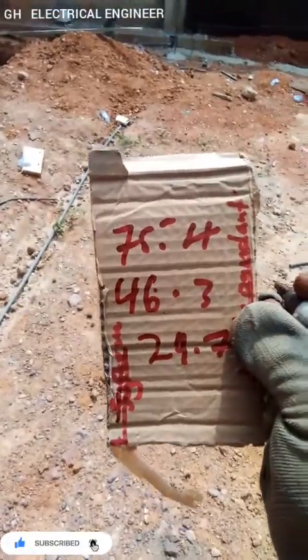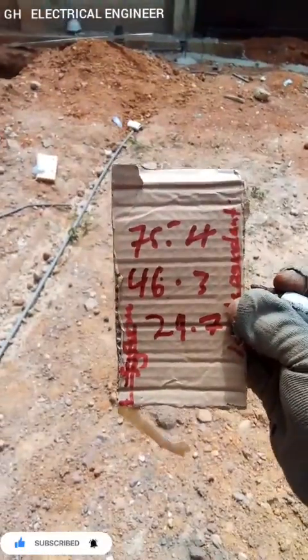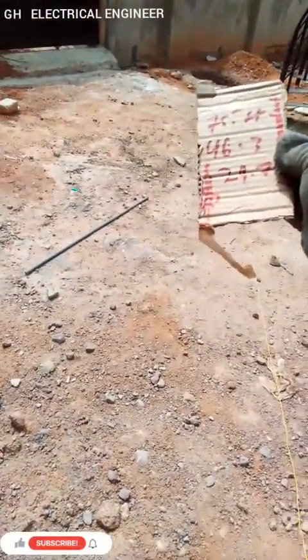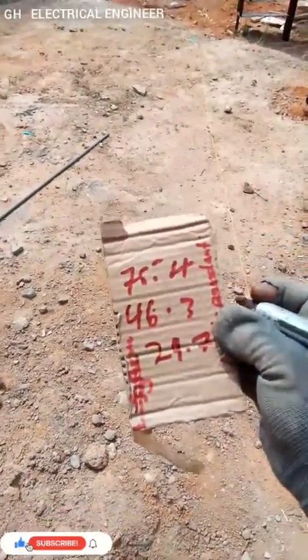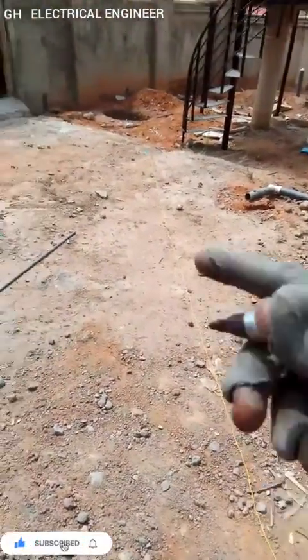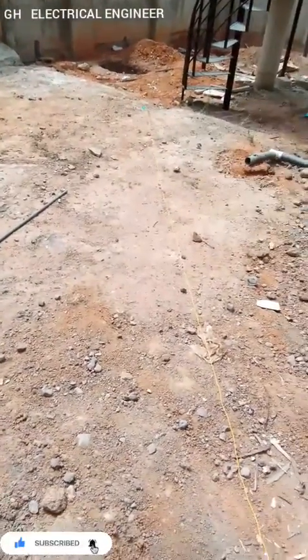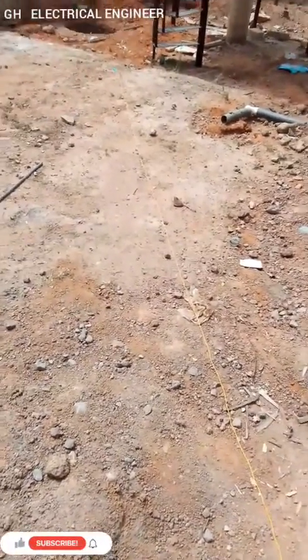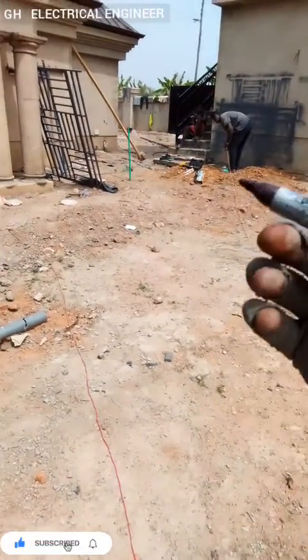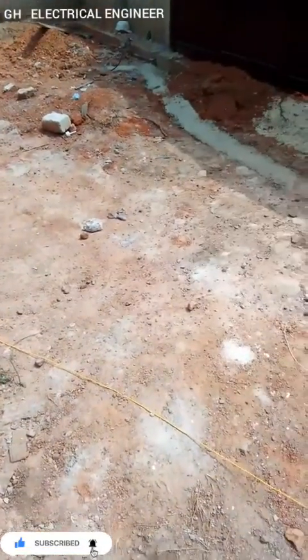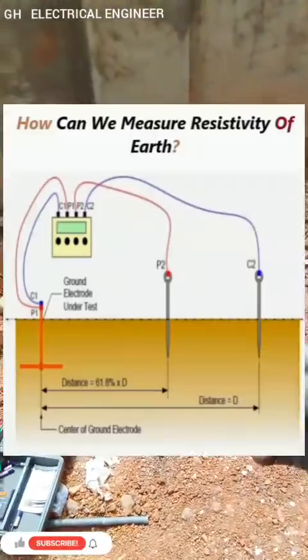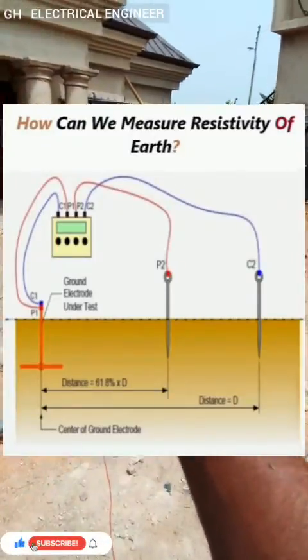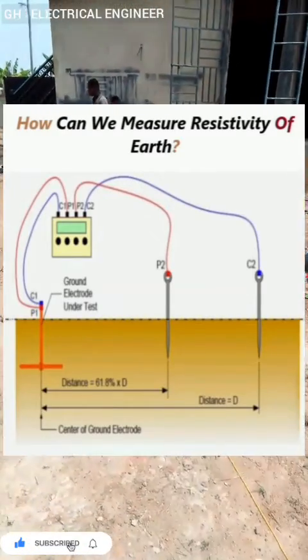That is why we continue to do more digging in the house, because we have to bury more earth rods. So what we are going to do, on this side we are going to test 2 of them right there. We bring the machine to that place, then take all the potential cable and the current cable to the opposite side and test it. What my guys is doing, as you can see, is using the potential cable and the current cable to unplug. You can see on your screen how this test is done.